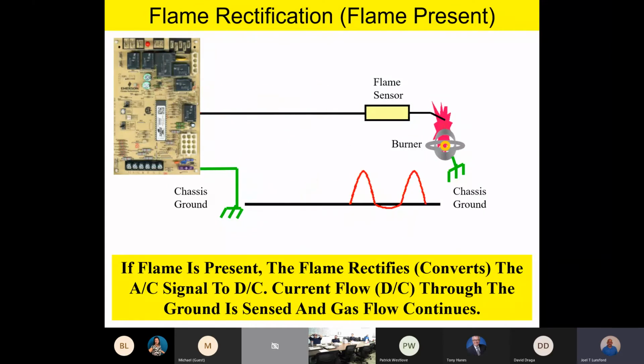So this is why it's so very important. If you wonder why grounding is so important on a furnace, this is why. If you don't have a good, clean, solid ground, the board cannot sense the flame. The chassis ground itself is the other side of that flame sensing circuit, as you can see in the graphic here. We have AC voltage going to the flame, through the flame, and then along the chassis ground we have pulsating DC coming back to the board, and the board senses that. If it sees pulsating DC or DC voltage on the ground plane, then it knows there's a flame present, and it continues to keep the gas valve open. So that's the basic science behind flame rectification.